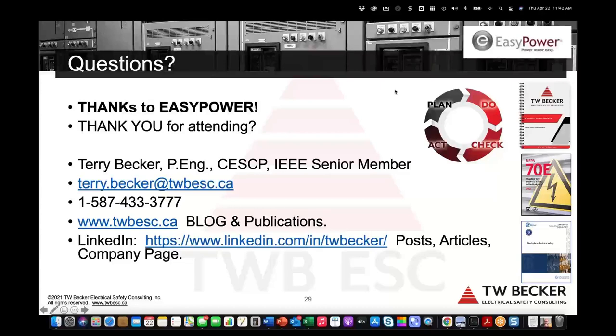So this question pertains to the 40 calorie reference. Virel says, is it not dangerous then above 40 calories due to physical injury and not burns? How does the definition of danger change? What's happened, and Jim and I have talked about this over the years, is that the arc blast pressure was unfortunately wrongly interpreted. There were some notes in 70E and Z462, and the original technical committee back then arrived at 40 cals, but it wasn't substantiated. Those notes were deleted two or three editions ago because arc blast pressure is based on arcing fault current. It has no direct correlation to incident energy.